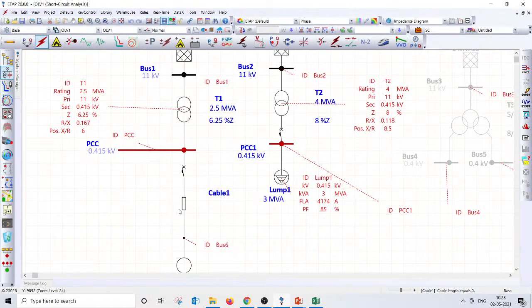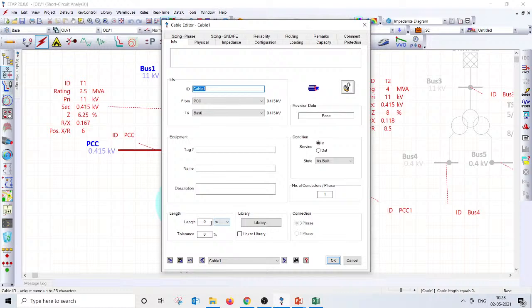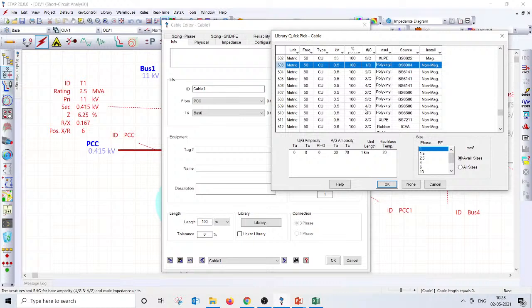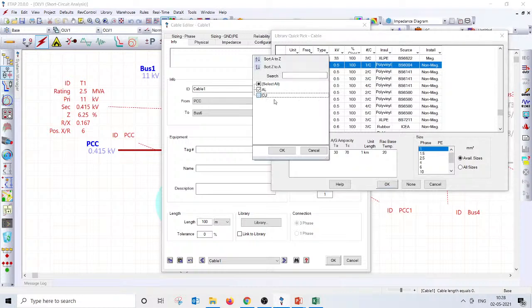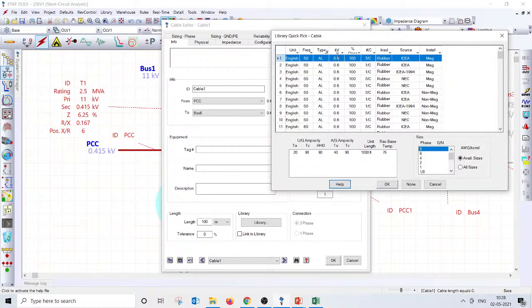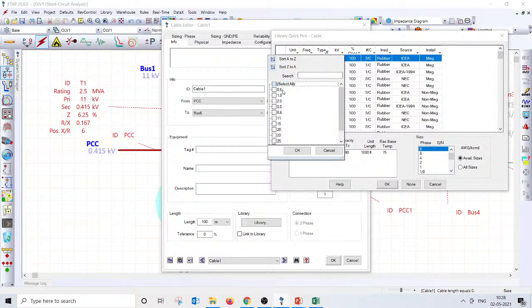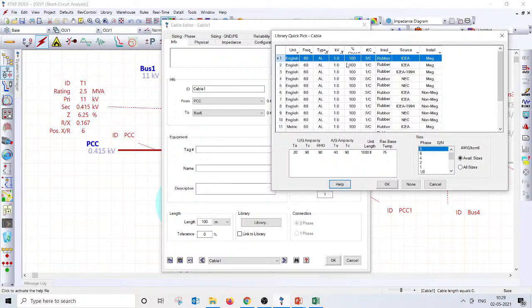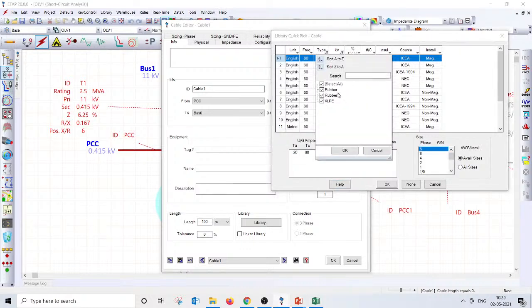Yeah, cable length, which I have not given, let me give a cable length as well. Say maybe let me take 10 meters, but 10 meters is too less. Let me take 100 meters. It depends on where your switchgear is placed and where your motor is connected.